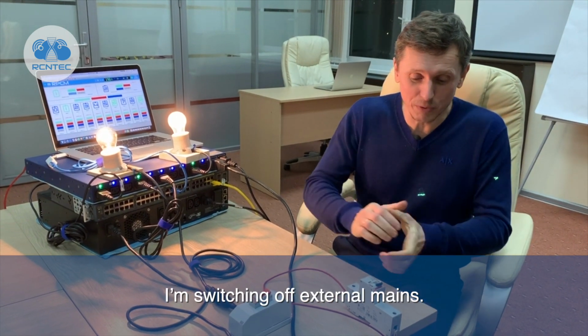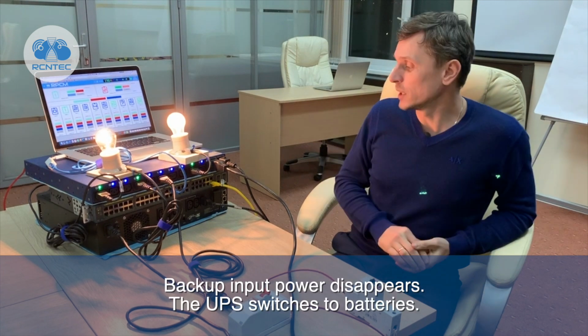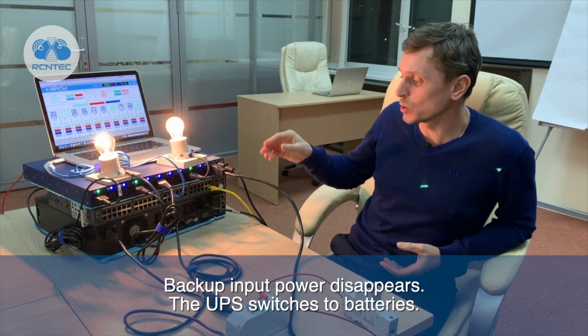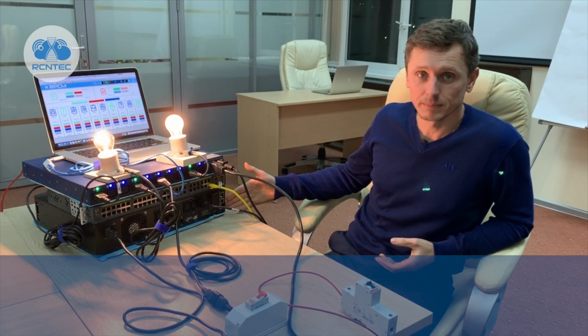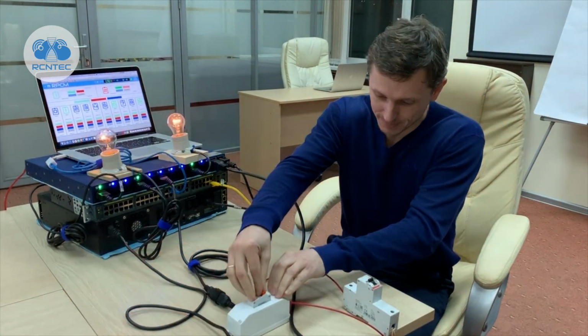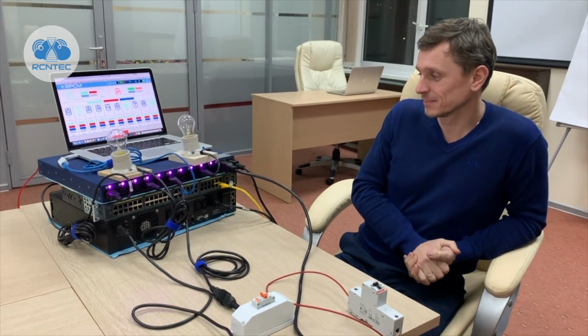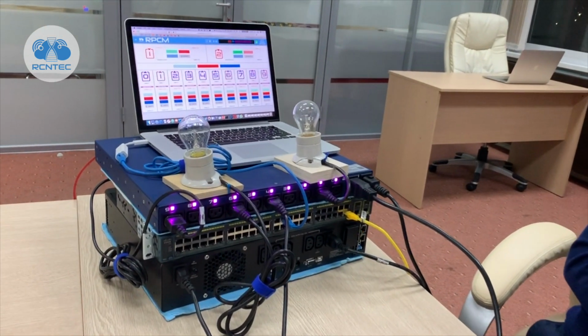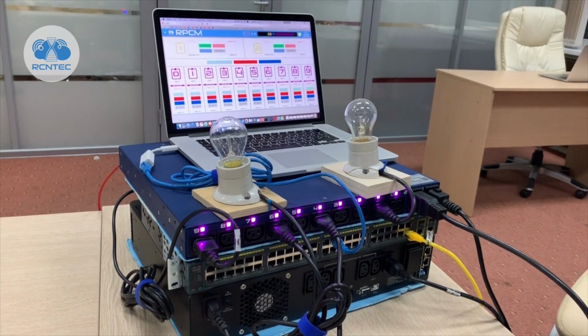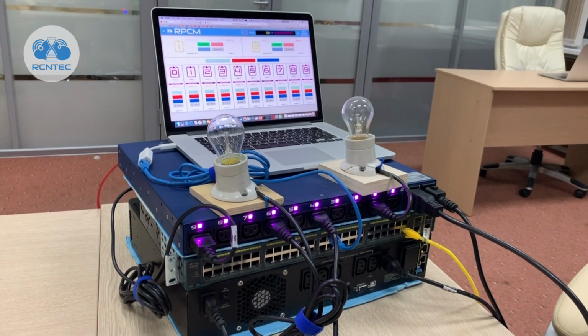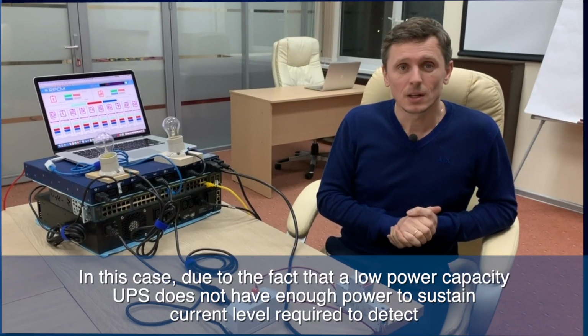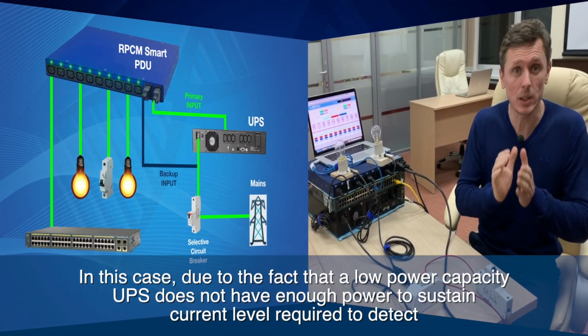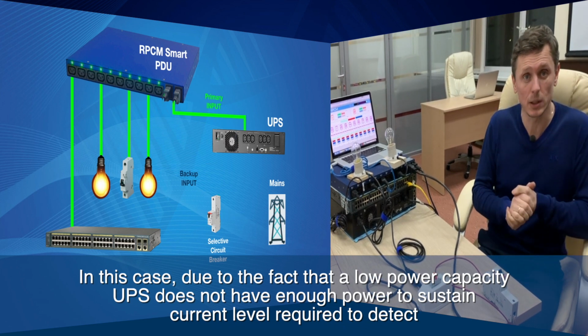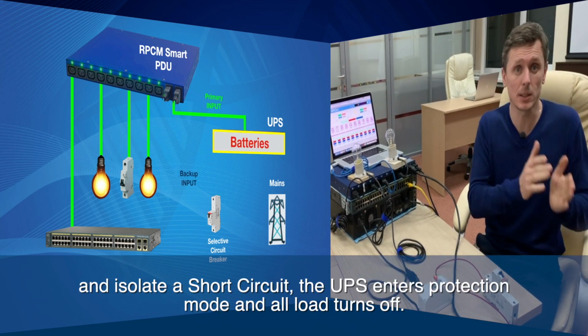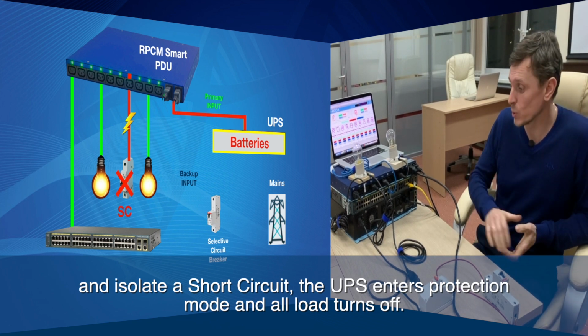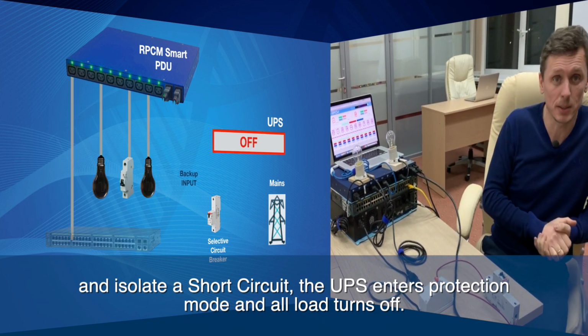I'm switching off external mains. Backup input power disappears. The UPS switches to batteries. Let's simulate the short circuit. In this case, due to the fact that a low power capacity UPS does not have enough power to sustain current level required to detect and isolate a short circuit, the UPS enters protection mode and all load turns off.